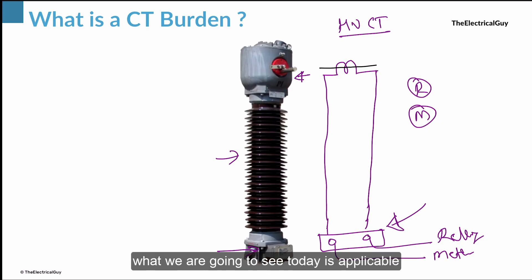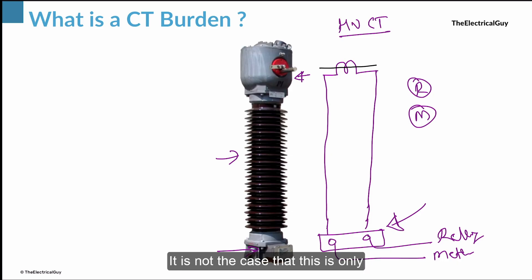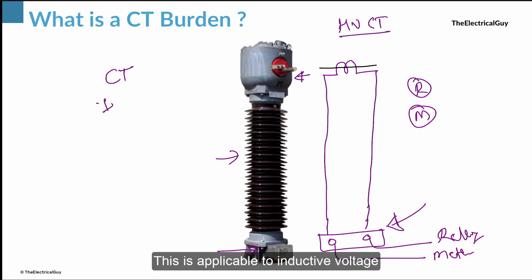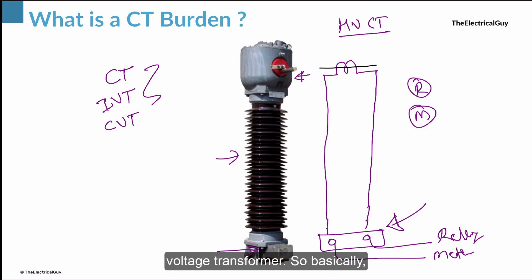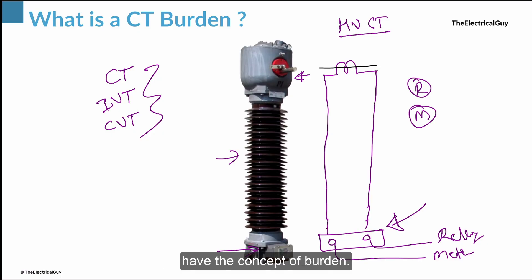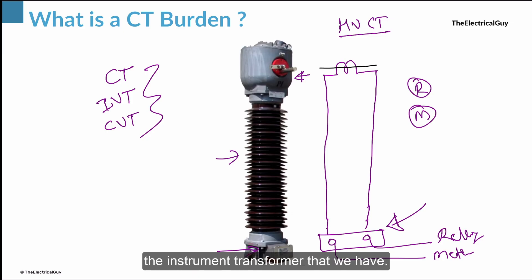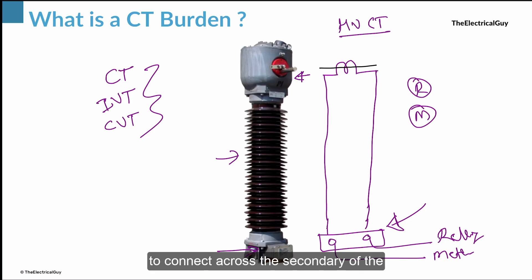This explanation is applicable for all instrument transformers — not only the current transformer. It is applicable to CT, to inductive voltage transformers, and also to capacitive voltage transformers. Basically, all instrument transformers have the concept of burden. In simple words, the burden is everything that we are going to connect across the secondary of the current transformer or any instrument transformer — it is essentially the total impedance.